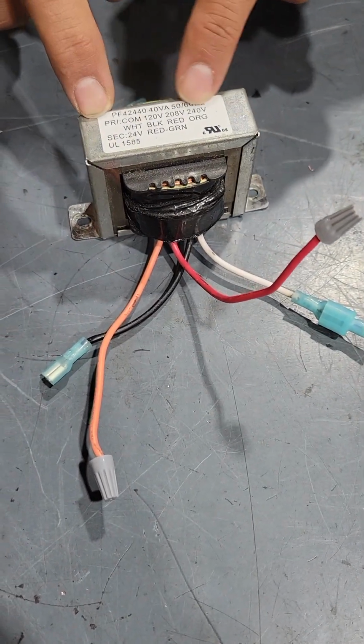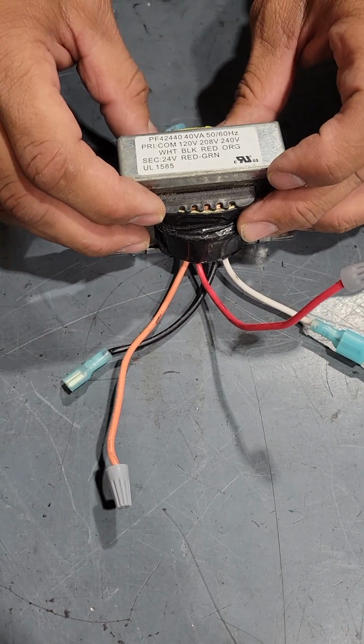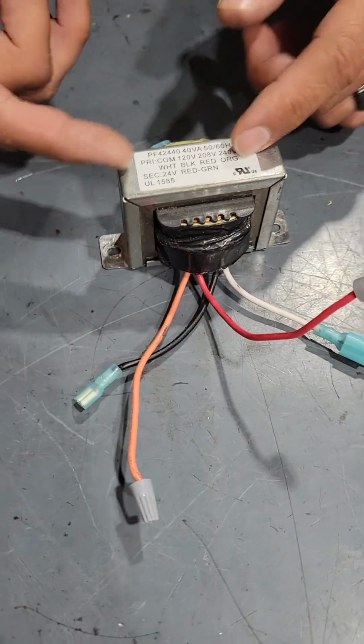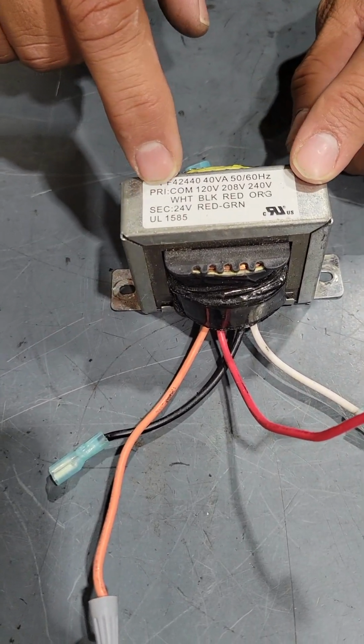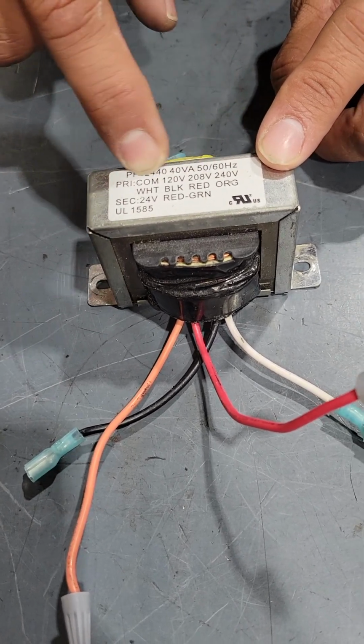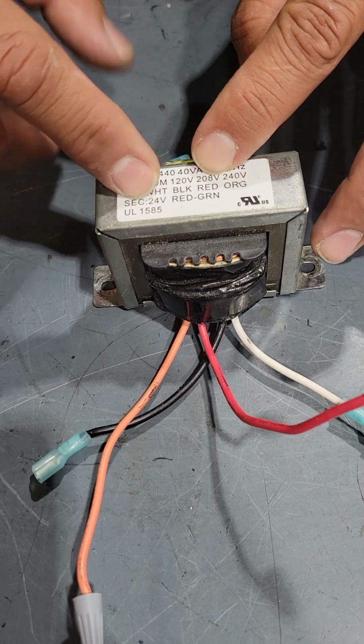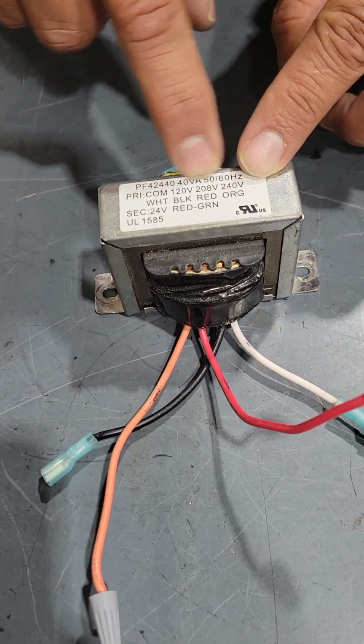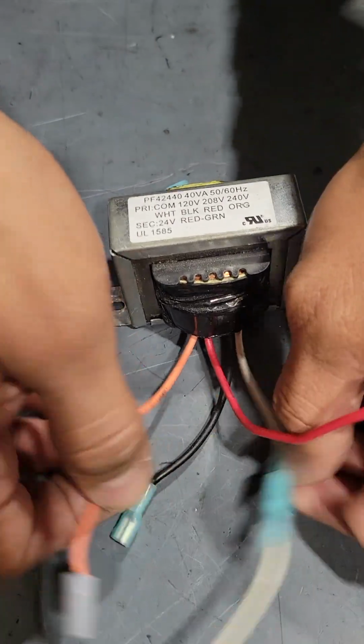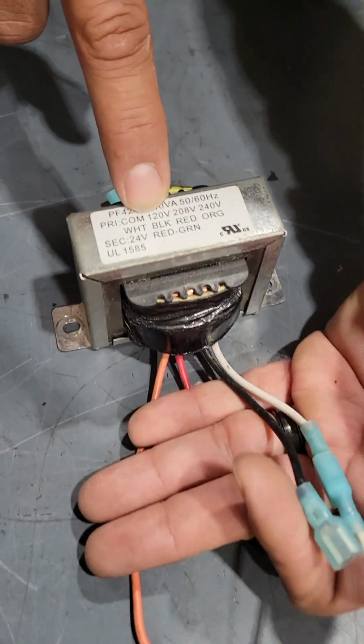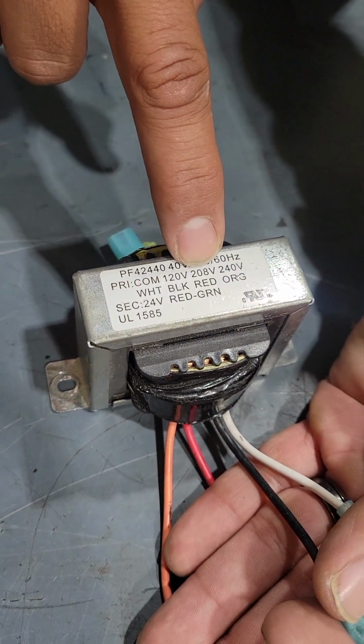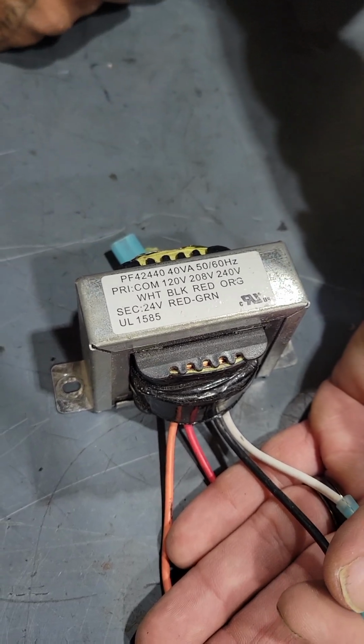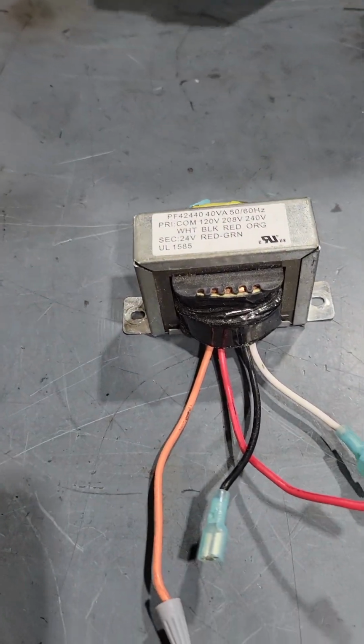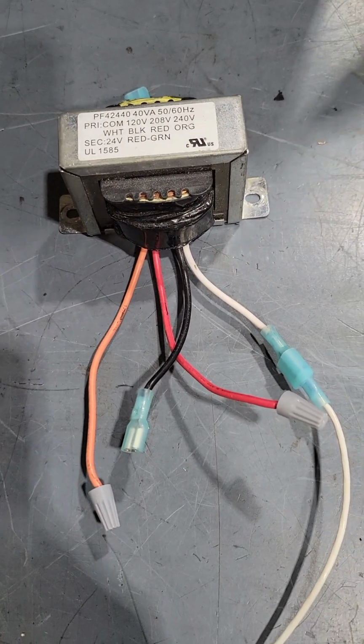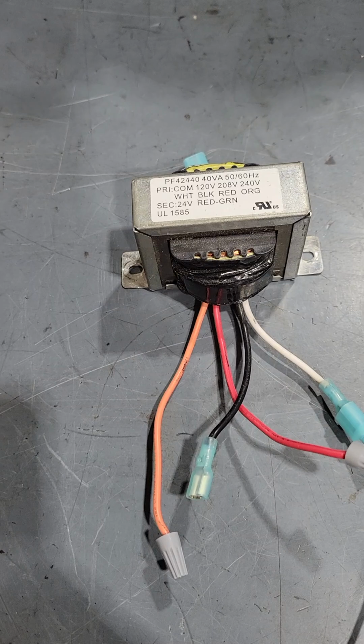Step down means it takes the original supplied voltage and induces it to a lower rate, 24 volts. If you had a step up transformer, that would mean your line voltage on the primary side, it would induce it to a higher voltage. So instead of 24 volts, it would induce it to a higher voltage than the primary. So let's say we're hooking up 120 volts to our transformer. Our secondary would be either 208 or 240 on this side instead of 24. That would make it a step up transformer. These are step down transformers. You typically don't see step up transformers in residential. It'll always typically be step down, so it'll be line voltage and secondary with 24 volts.